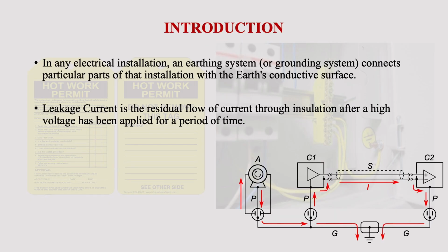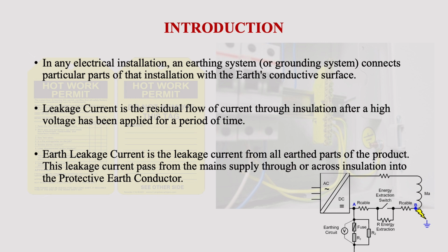Leakage current is the residual flow of current through insulation after a high voltage has been applied for a period of time. Earth leakage current is the leakage current from all the earth parts of the product. This leakage current passes from the mains supply through or across insulation into the protective earth conductor. Mind that we are looking at the earth and grounding systems for industrial safety from the regulatory point of view.